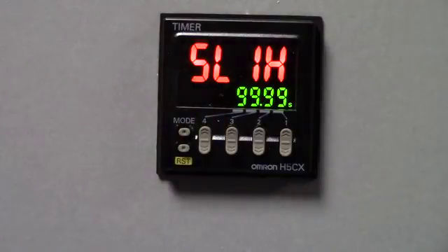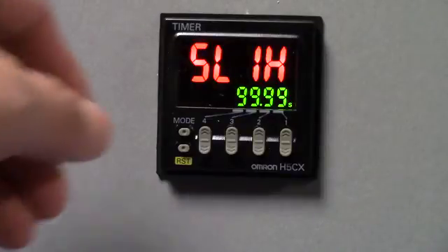SL1H. This is going to allow you to set the upper value limit. The factory default is 9999. What this allows us to do is set the ceiling for your upper limit timing, so it will not go past that timing sequence. Given today's video, it's okay to keep it at the factory default of 99.99 seconds.